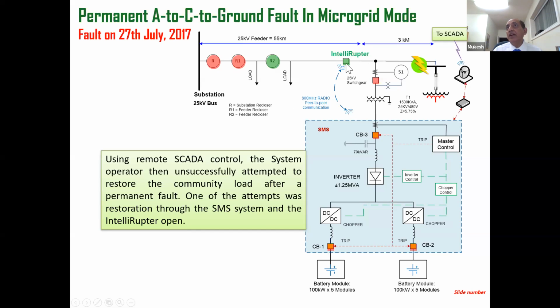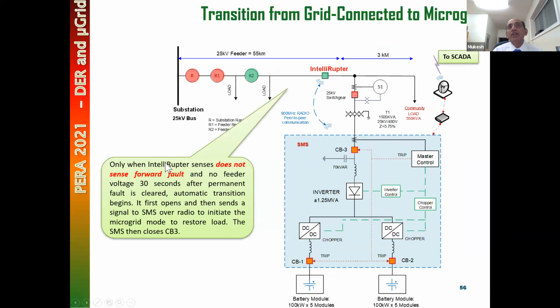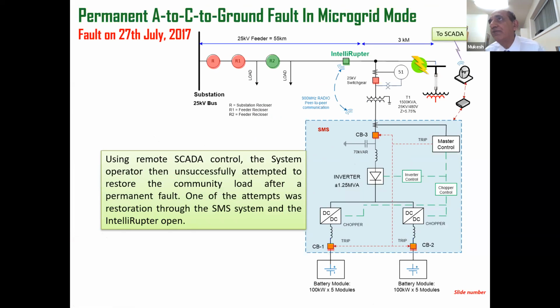Once the reclose attempt has failed, after 30 seconds, this interrupter sees there's no forward fault. It says, I did not see a forward fault, and I see the voltage is gone for 30 seconds. That means the reclose attempt has failed. Then it signals this inverter to go into grid forming mode, form a microgrid and supply the load. So for a fault here, it cannot do anything, but for a fault here, it gives a signal to this, and it can form a microgrid.